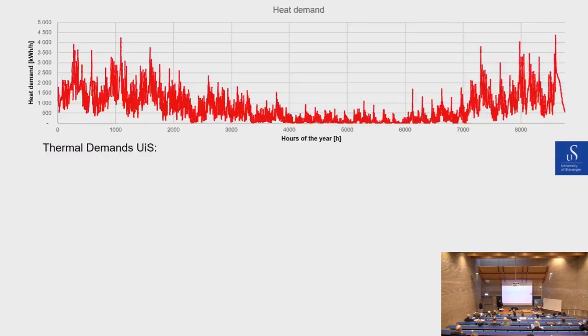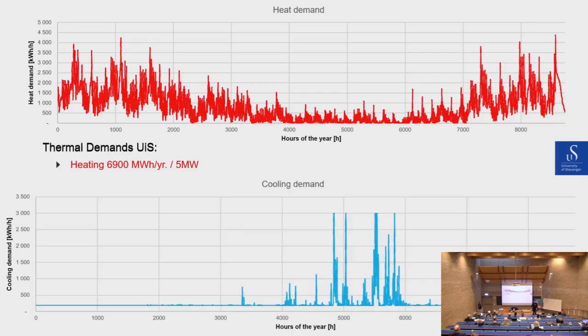Some words on the demands. Here you see the heat demand curve. It's obvious when you think about it, but the heat demand is mainly related to the climate, to the temperature outside. On the coldest days, our maximum demand is about 5 megawatts, and the total heating demand is 7,000 megawatt hours per year. For cooling, the demand is most of the year very low, about 200 kilowatts, and then there are some high peaks. These curves are very important for the design of the system, determining the size of the heat pump and how many boreholes you need.